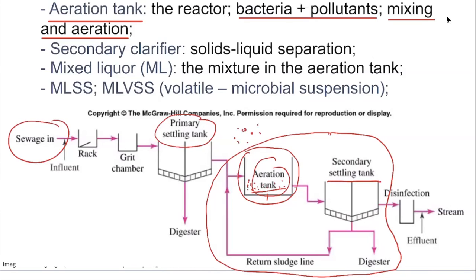While they populate, when they get more of them, they're going to aggregate. They're going to collide with each other and form larger chunks of bacteria, or you can also call them colonies, right? When their mass grows larger, they're going to basically settle down onto the ground. So we can use this way to remove these larger bacteria or these suspended solids down to the base of the clarifier.